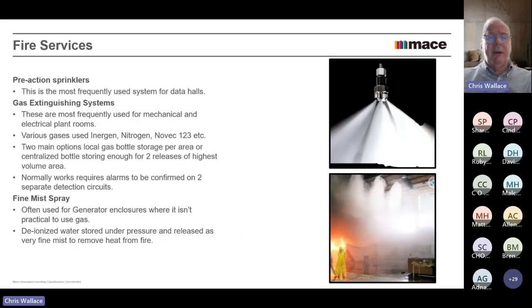Very quickly on fire. Most of these use pre-action sprinklers. There's a sprinkler system where you don't fill it with water. The actual range pipe is full of compressed air. In the event of two knocks in the fire system being picked up, you evacuate the compressed air from the line and allow the line to charge with the sprinkler water. The sprinkler won't go off until the sprinkler bulb is burst by the heating of the bulb, and you don't get water into the data hall. You will only get water into the data hall if you get two knocks on the fire, you get rid of the compressed air in the system and you fill it with water, and the sprinkler goes.